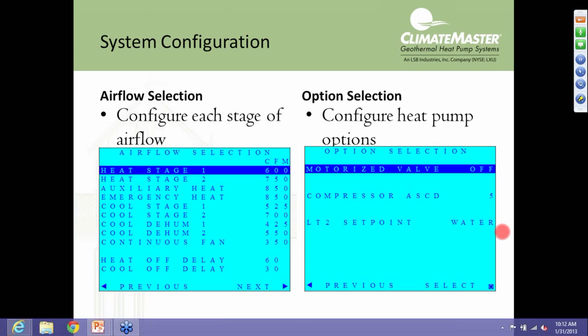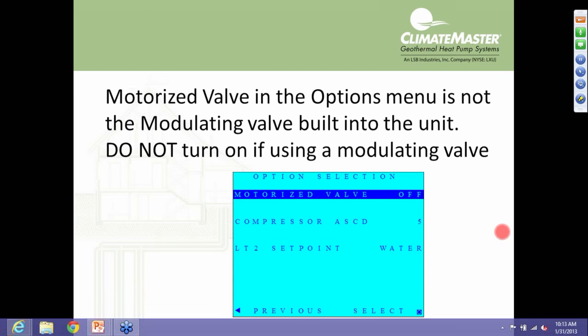Again, if it was a water-to-water product and we actually had antifreeze on the load side, we could then change this set point from where it says water here to where it'll say loop. Again, just emphasizing that top one highlighted there, motorized valve. This is not the modulating valve inside the heat pump if your unit has one of those. This is for an external solenoid valve. And again, in most applications, you need to leave this in the off position unless you're installing an external valve.